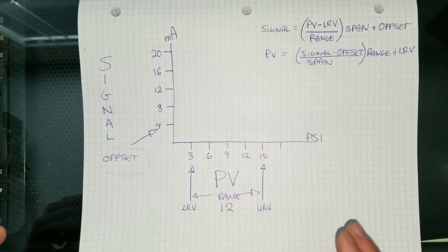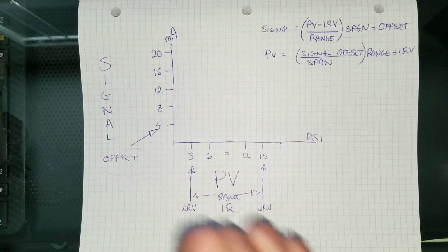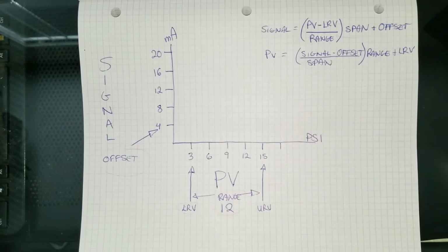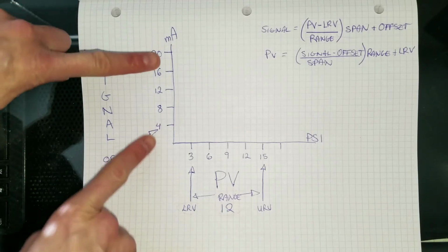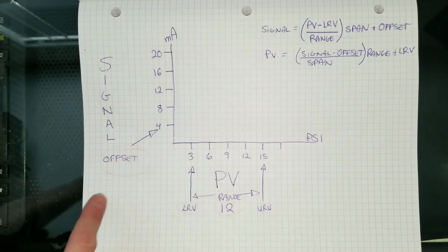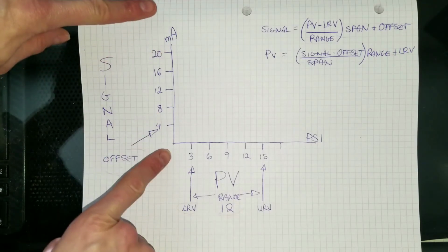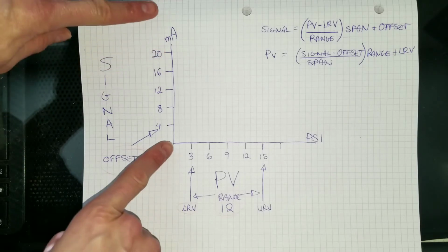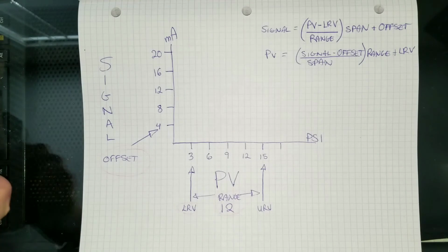So then the instrument span, when we give it the 20 milliamp signal, when we adjust the span on the instrument, we want to see 15 psi out. You're going to see in the other video that when I adjust the span, I'm adjusting this. And you're going to see that we go back and forth between the 2, 0, and span so that we can calibrate it. Because every time we adjust the span, we do this. Every time we adjust the 0, we're doing that. So you can see that one will adjust the other. So we're going to go back and forth for calibration.